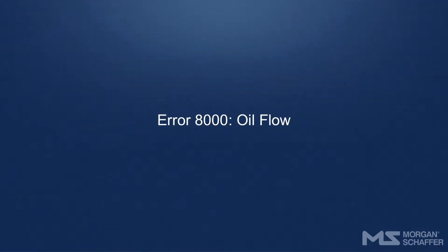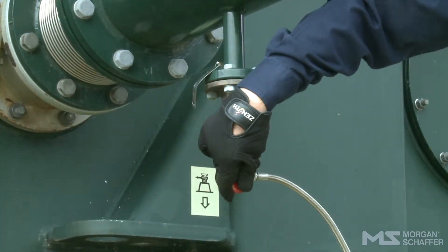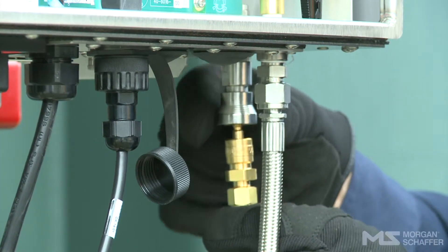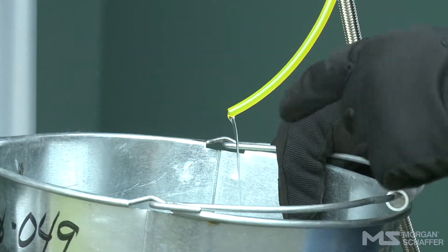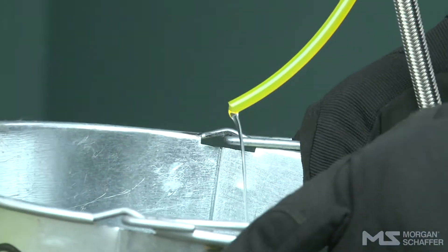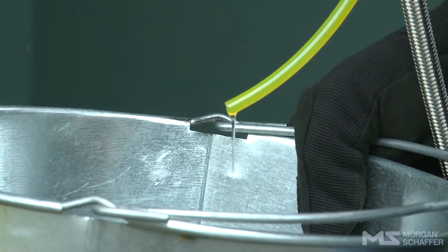Error 8000 – Oil Flow. This error occurs when the oil flow falls below a predefined level. Check that all valves are open — transformer and Callisto. Take an oil sample using the Quick Connect oil sampling tube and check the oil's viscosity. If these items are in order, please contact Morgan Schaffer for assistance.